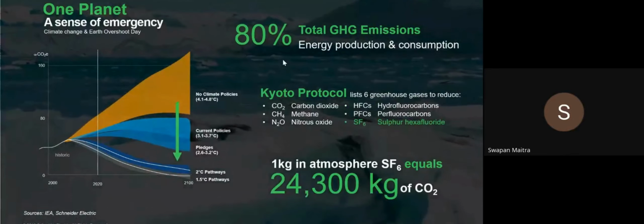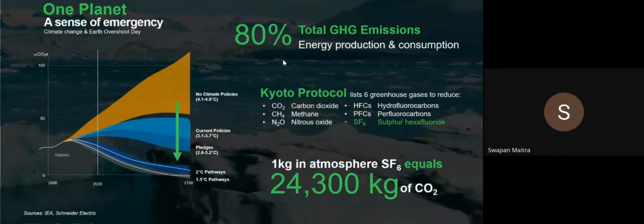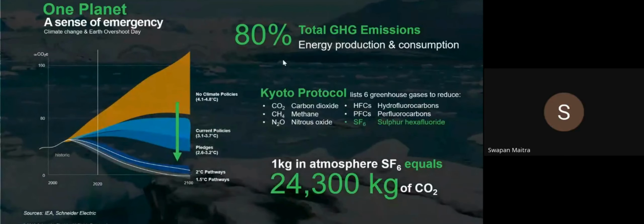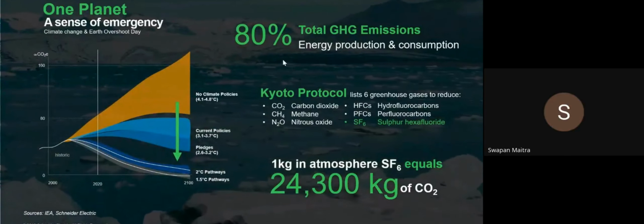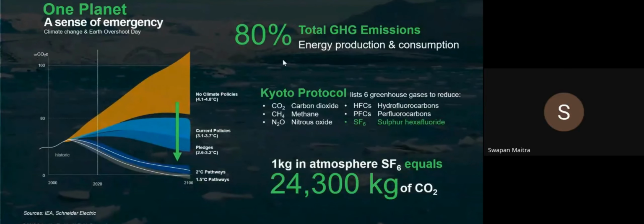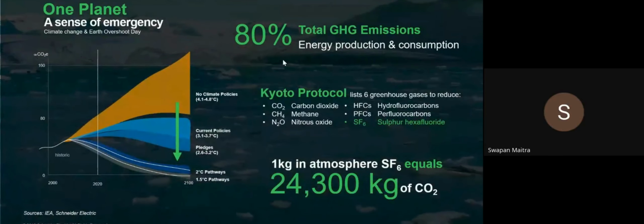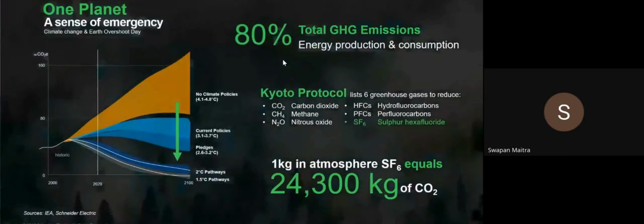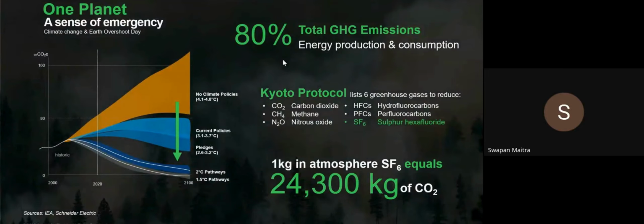We have to slowly move away from this SF6 technology. We are ready with pure air as a substitute for our 33 kV equipment. We are not there beyond 33 kV, so up to 33 kV and 11 kV RMU, we have come up with a substitute for SF6, which is pure air.